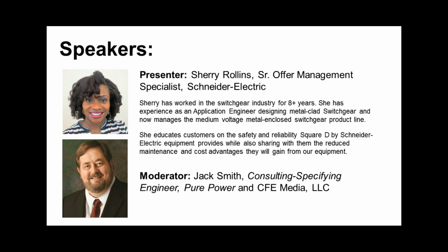Trying to keep this as generic and have an industry discussion on fixed versus withdrawable, it's really going to depend on the manufacturer and their design. But I can tell you, in our portfolio, we can have the same number as you do on withdrawable. It's just really going to depend on your needs. So if you need 4 CTs per breaker, we do have a fixed mounted design that can have 4 CTs per breaker, just like you see on withdrawable.